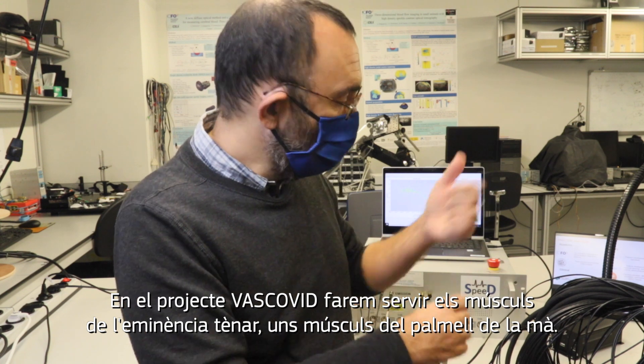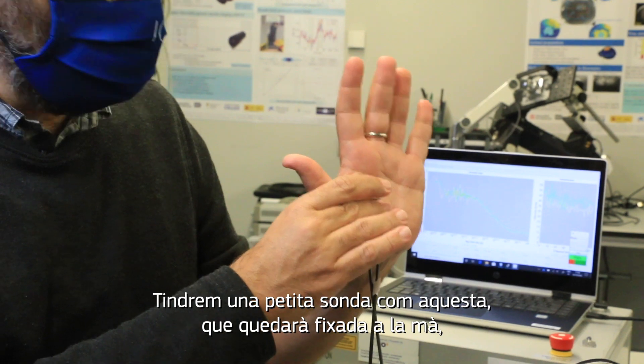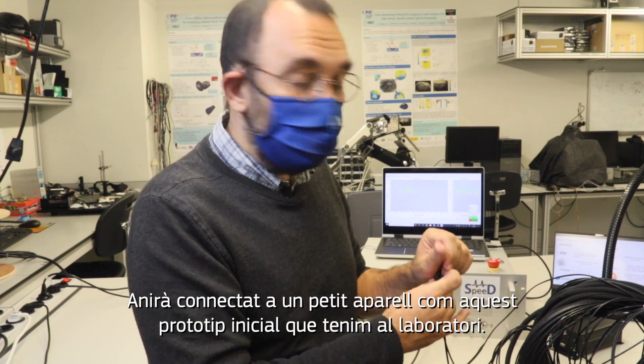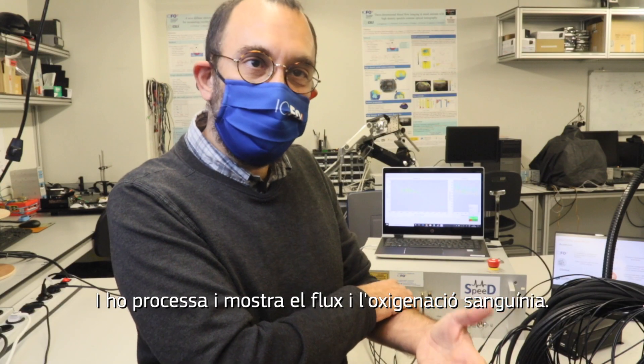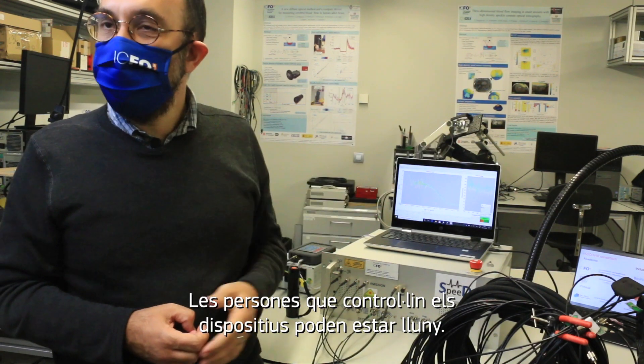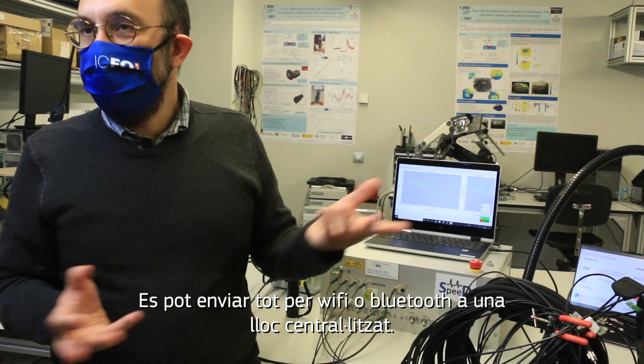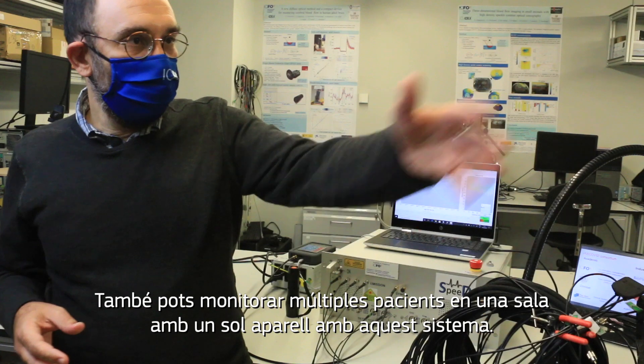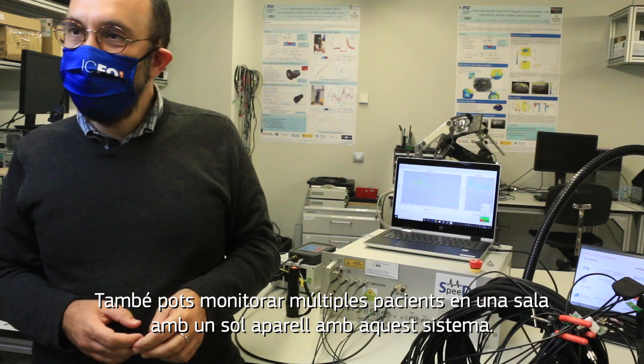In the VASCOVID project we will use the thenar muscle, which is the muscle inside the palm. We'll have a small probe like this that will attach to the palm, but we'll work it with a wireless device. This will be attached to a small device like this early prototype that's in our lab, and that processes it and displays the blood flow and blood oxygen levels. Everything can be sent by Wi-Fi signals or Bluetooth signals to a central location. You can also monitor multiple devices in multiple patients in the room with one device by doing this type of work.